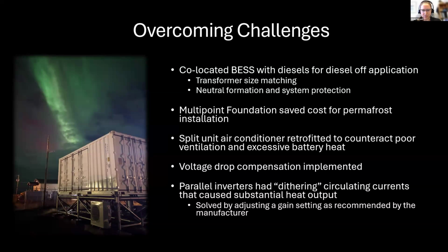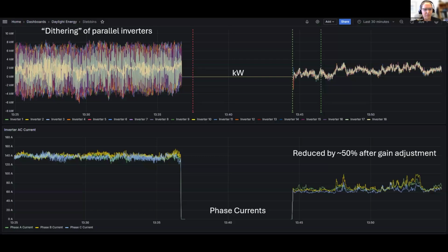We call it dithering - essentially, you can see on the left where all of these devices were fighting each other. Once the right set point change was made, the kW output smoothed out significantly. They were no longer fighting each other, and we actually saw 50% of the amount of current on that same system of inverters, cutting it in half.